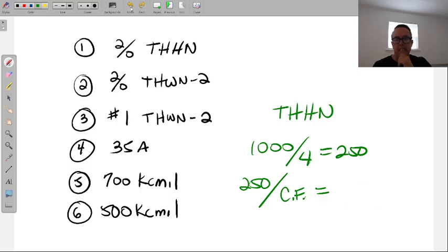And for the correction factor, we take all the wires? Exactly. Just 8 current carrying conductors in the conduit. The number 8 is what we're factoring the correction factor around. This is the number we've been using so far. I didn't try to complicate this too much, so we should be looking at 0.70.